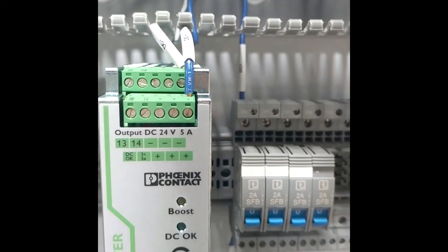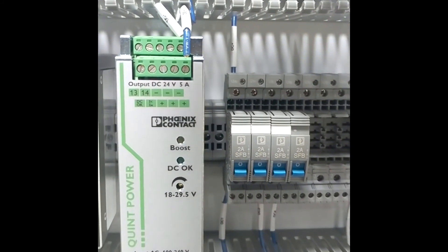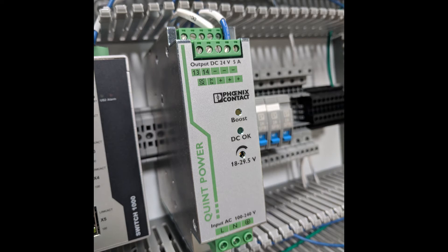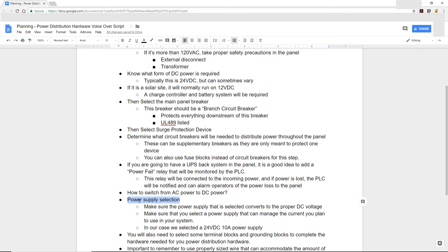Next, we want to look at how we're going to convert our AC power to DC power — in this case, we're going to use a power supply. There are a lot of different brands you can use; we're going to use a Phoenix Contact power supply, specifically a 24 volt DC, 10 amp unit. We want to make sure the power supply we select converts to the proper DC voltage — whether 12 volts, 24 volts, or whatever it may be — and that it can manage the amount of current we plan to run through our particular system.